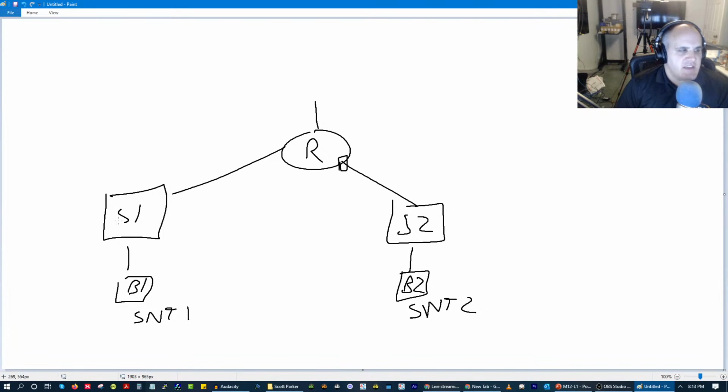Okay, so our broadcast cannot leave our subnet. Now with BACnet, that's not necessarily true, and we'll talk about that. Now, as I mentioned, we have default gateway. Default gateway can be any address in the subnet range, although it is usually the first, and the broadcast address has to be the last address in the subnet range.